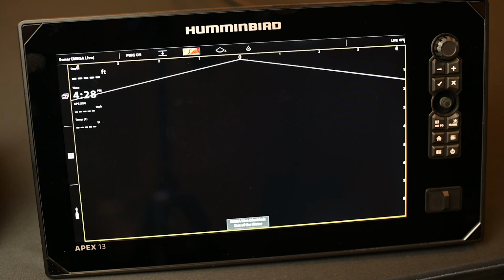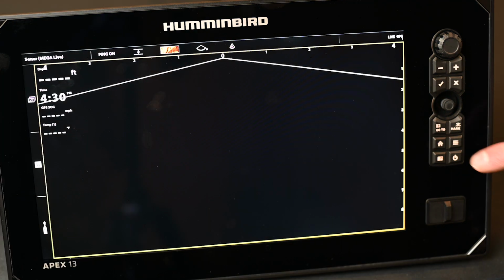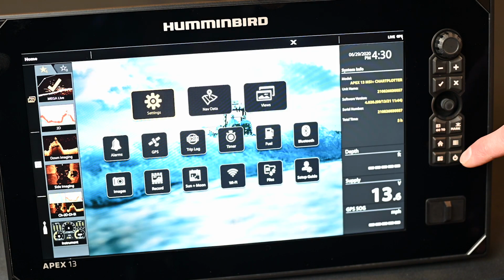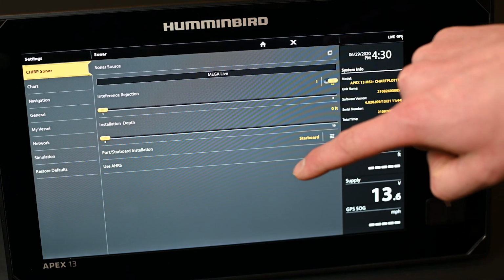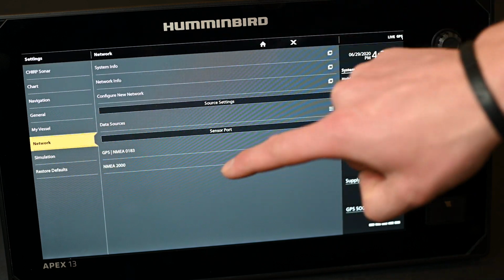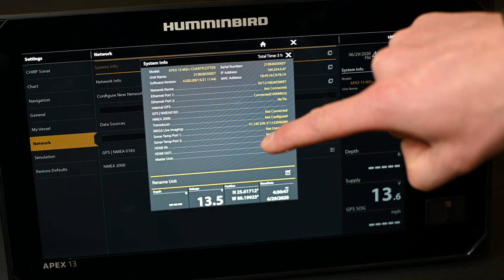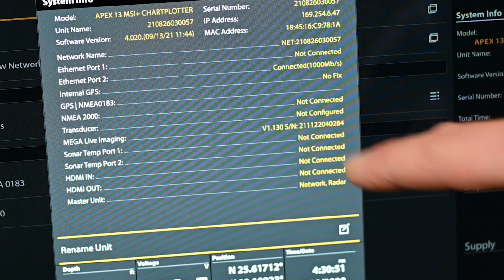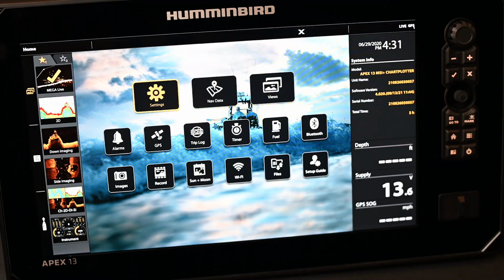We will check the version of the MEGA Live firmware. This screen can be found from the home screen by tapping Settings, then Network, and then selecting System Info, in which we will be able to confirm the current MEGA Live firmware version. Now that we've confirmed we have a compatible previous firmware version on the MEGA Live transducer, we are ready to begin the install update. We'll start this process by inserting the SD card into the Apex or SOLIX unit.